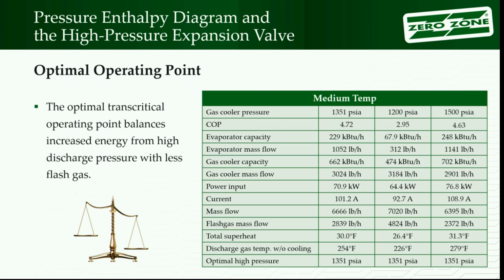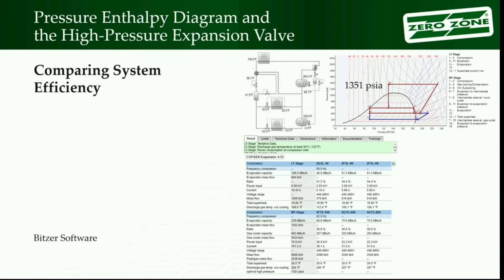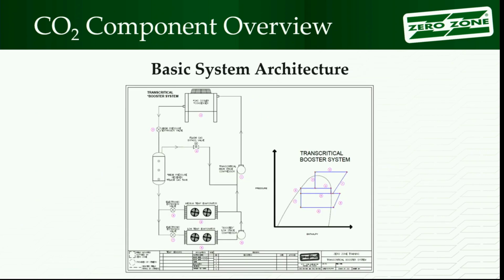The one thing, and let me just scan back, I do want to touch base on the system here. When you're doing troubleshooting on a system, this is just sort of true, but maybe you don't think about it. Those compressors, if you have medium temp evaporators, that high stage is going to have 3 different gas flows. So you're going to have gas flowing out of your gas cooler, you're going to have gas coming out of the evaporator, and you're going to have gas coming up from the discharge of the compressor. So if you're working on superheat, I got too much superheat, I got too little superheat on that compressor, you need to think about what's going on with those 3 different mass flows, right? So that's why that temperature dropped, because this is really cold compared to the other 2. As I put more really cold gas into that mixed stream, it pulls down the suction temperature of that compressor. So something to be aware of.